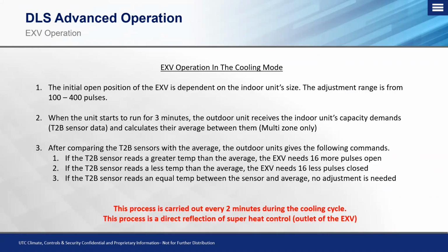Okay, so we look at the EXV operation in the cooling mode. The initial open position of that EXV is dependent on the indoor unit size. So it'll differ between a 9, a 12, an 18, a 24, and so on and so forth. That adjustment range for pulses is from 100 to 400 pulses.